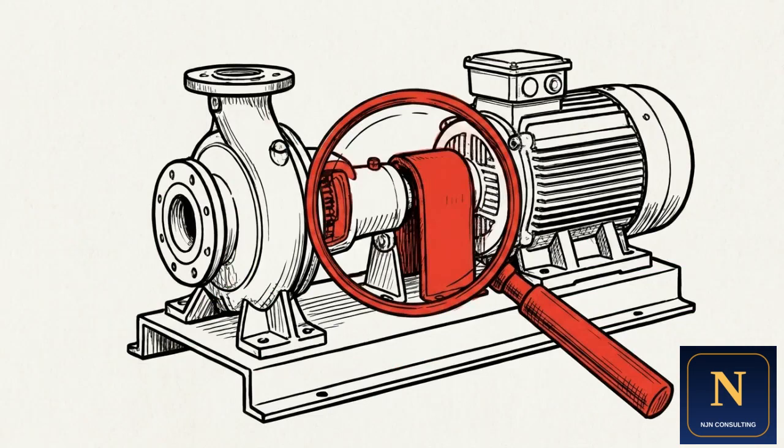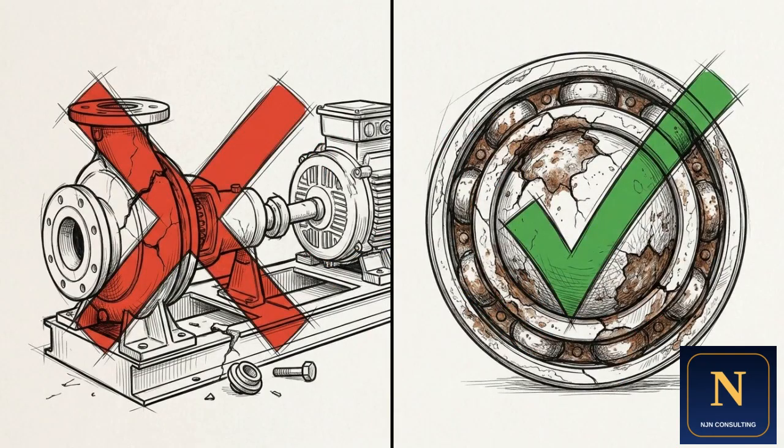For those high-risk assets, we have to isolate exactly what goes wrong. We cannot use vague terms like pump failure. We need highly specific descriptions of how the component fails its intended function. This table is a FMECA worksheet. First, we list the function. Next, we map the precise physical failure mode.